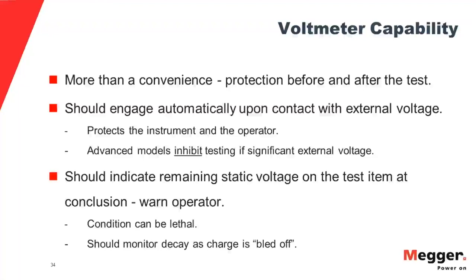Not only will they tell you, but they will also prevent the operator from energizing the tester if there's voltage on the test item. So when you're buying a tester, make sure that it has that capability. Otherwise, you're liable to lose it relatively quickly, like first day on a job. So they will inhibit testing. And the other thing that they do, that's at the beginning of the test or during the process of the test, because sometimes someone will go and throw a switch, which you have turned off but didn't lock out, for instance.